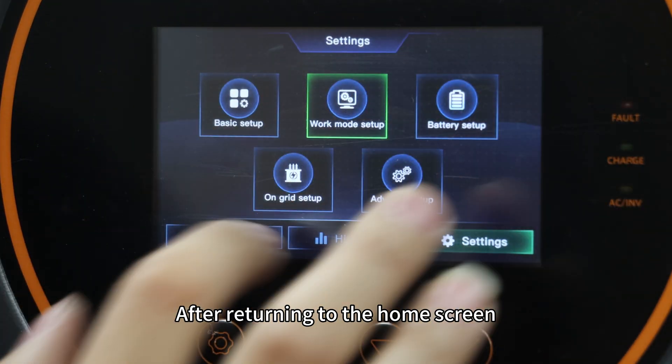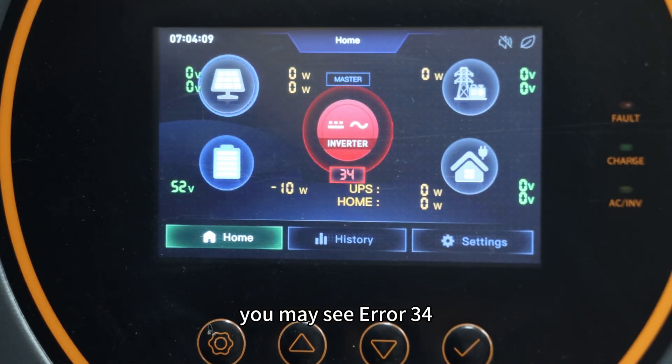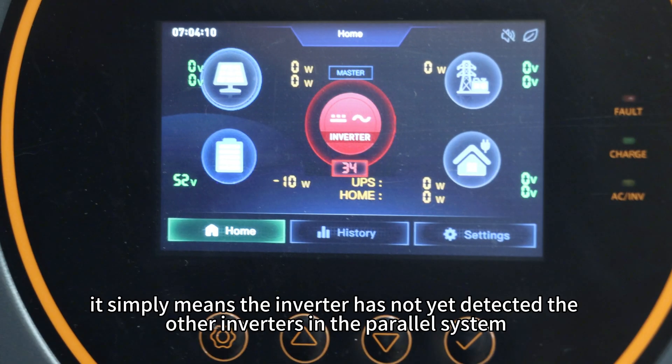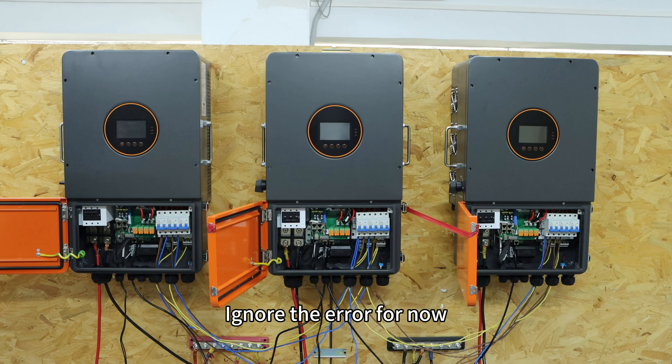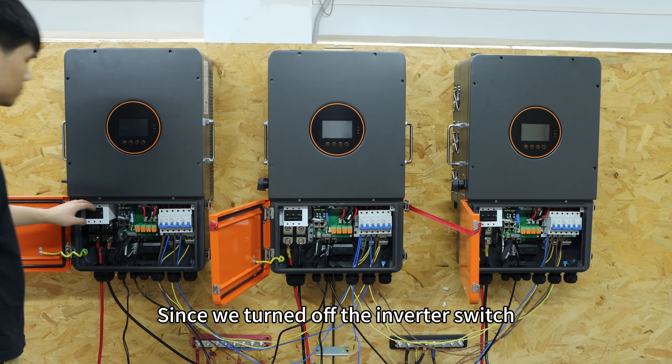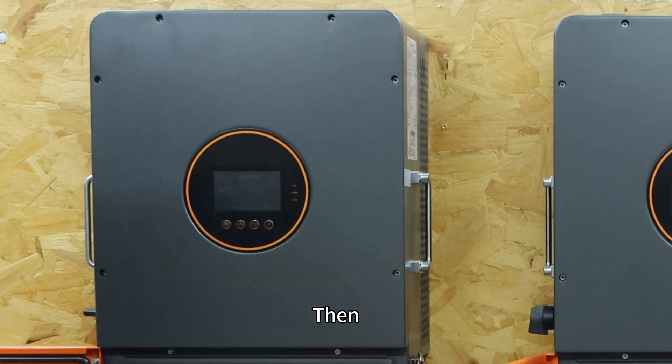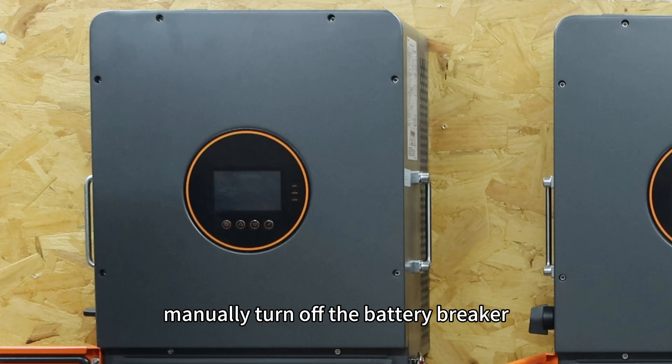After returning to the home screen, you may see error 34, CAN communication fault. This is normal — it simply means the inverter has not yet detected other inverters in the parallel system. Ignore the error for now. Since we turned off the inverter switch, it will automatically shut down after a short time; then manually turn off the battery breaker.